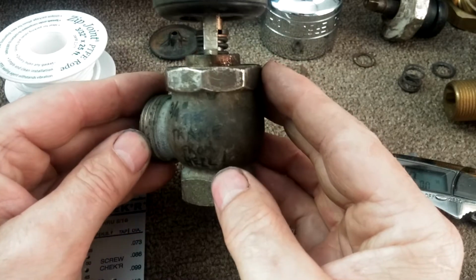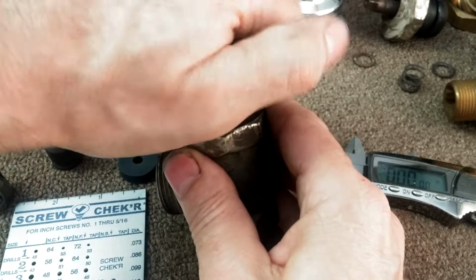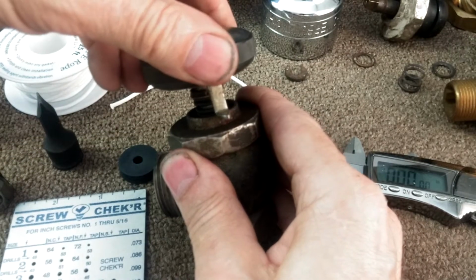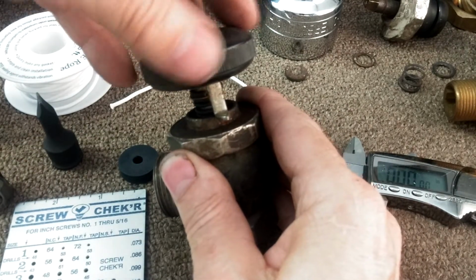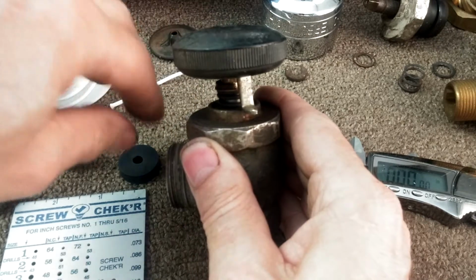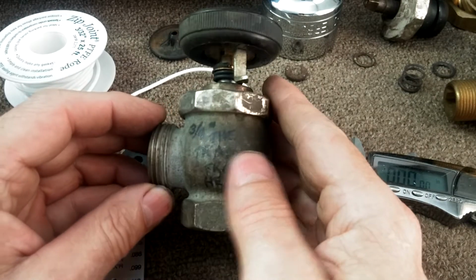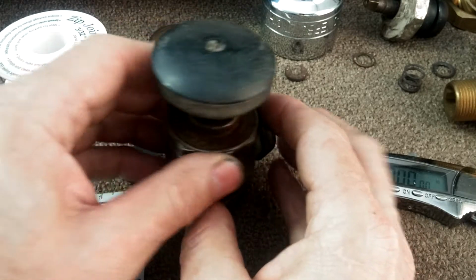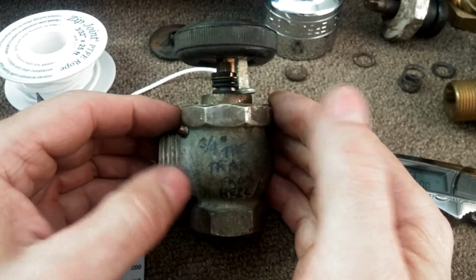One of the reasons why you would confront this valve is that most of the time it is locked, doesn't turn, or turns very slowly and reluctantly, and the material inside the washer is sufficiently decayed as to no longer shut against the steam. So let's break this down and see if we can find out its secrets.